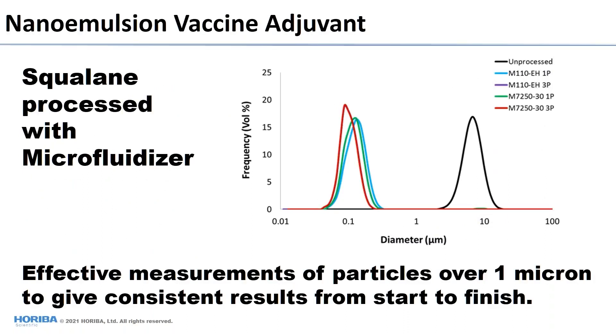A squalene run through a microfluidizer shows that the unprocessed material was about 10 microns. After the first pass you can start to see a peak at around 100 nanometers. Looking at different formulations and multiple passes — with three passes you can still see a little residual material at the 10 micron range. The advantage of the LA-960 is that you're able to look at your entire process from the starting material at 10 microns, which is too large for comfortable dynamic light scattering, all the way down to about 100 nanometers, with consistent results from start to finish using only one analyzer.